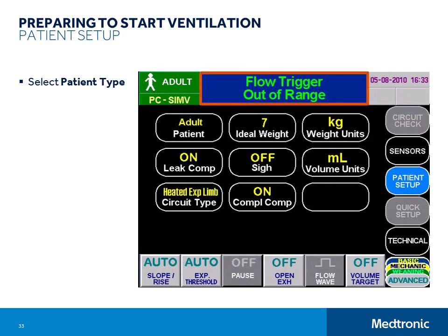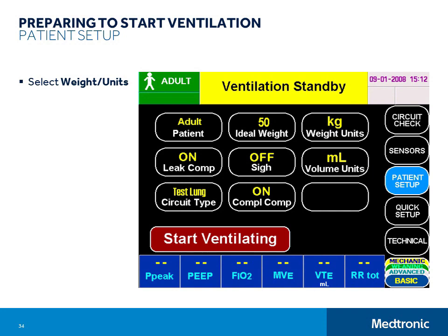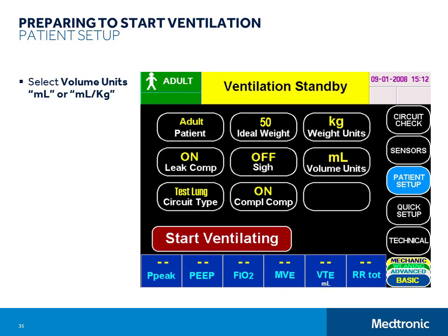The next step is to select Weight Units and Weight. If you intend to use the Quick Setup function for determining start-up ventilation and alarm settings, you will need to enter the patient's ideal body weight, which is calculated from their height and gender, and select the weight units in pounds or kilograms. If you do not intend to use the Quick Setup function, you can skip this step. If you have entered an ideal body weight, you can also choose to display exhaled tidal volume numeric displays in mL/kg instead of mL. Next, set the Sigh function on or off. The Sigh function gives a Sigh breath every 100 mandatory volume control breaths. The Sigh tidal volume is 1.5 times the set tidal volume.